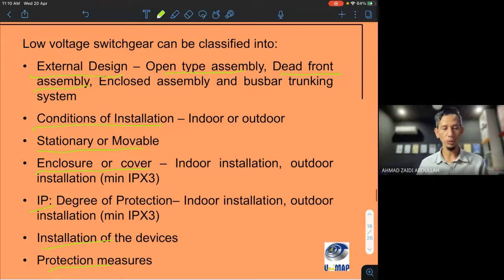And then condition of installation, whether you want to design it for indoor or outdoor. So if you are planning to design the MSB or your distribution board to be installed outside of the building, it must refer to the standard for outdoor. So this one depends much on the condition of the installation. And then is it movable? We also have portable MSB.